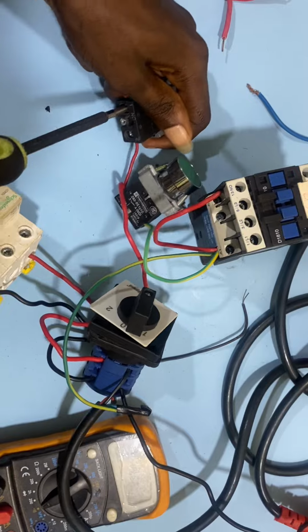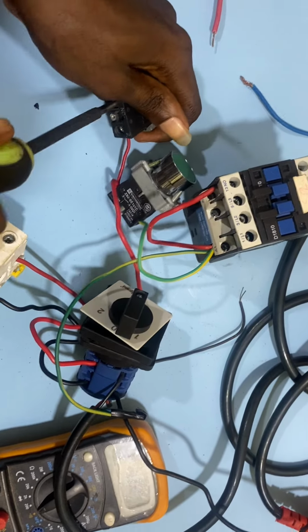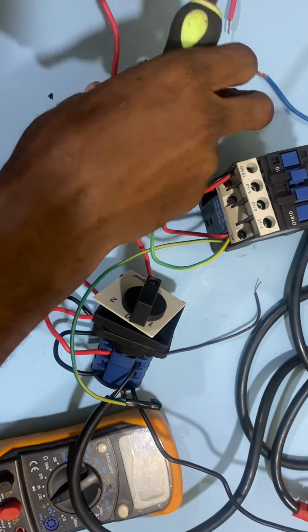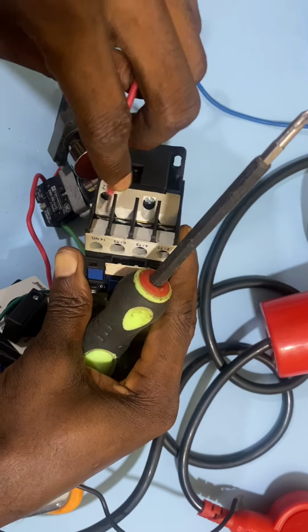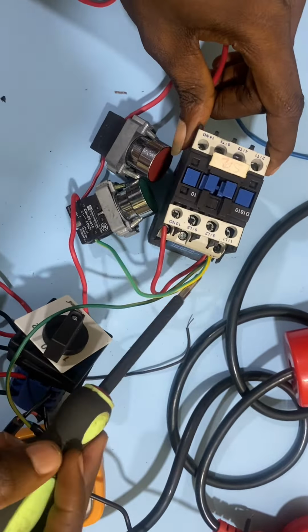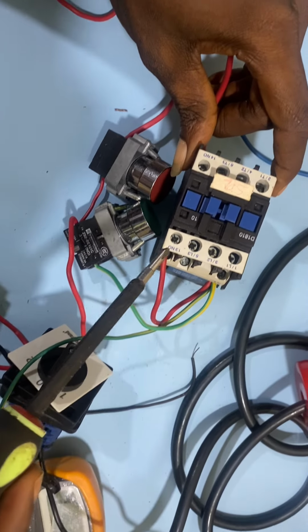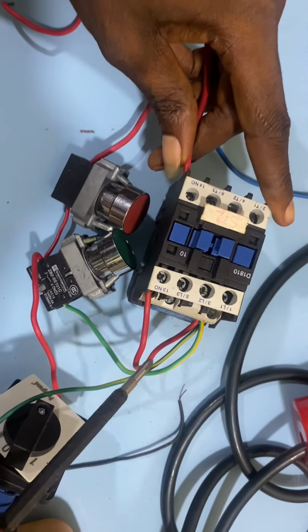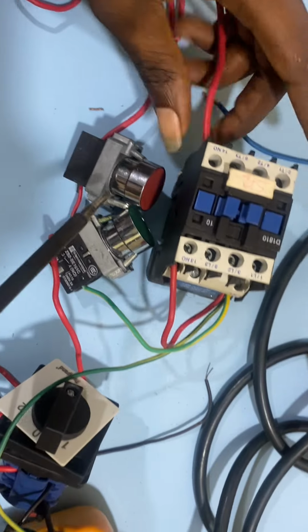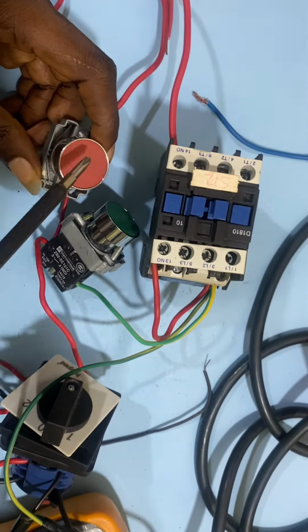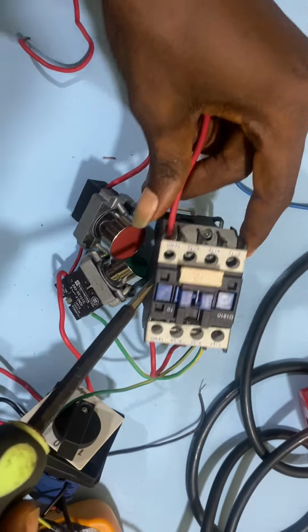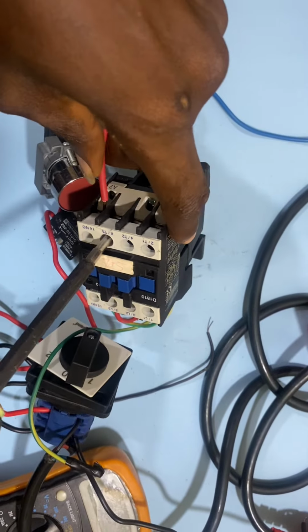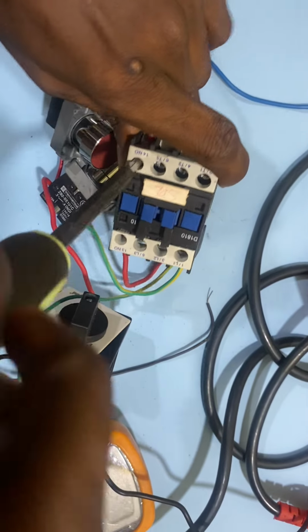You know that stop button is always normally closed, initial condition. So that is it. So I'm going to take it to contactor normally open. Know that the first one was from my A1 contact to normally open 13, and that one was from the start button, and this one is from the stop button. So stop button to normally open contact 14. So at contact 14, my contactor. Alright, so I'm done with that.